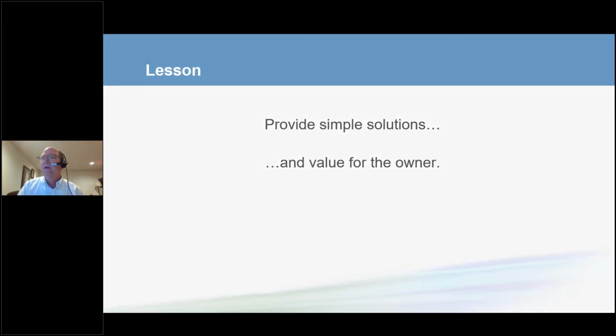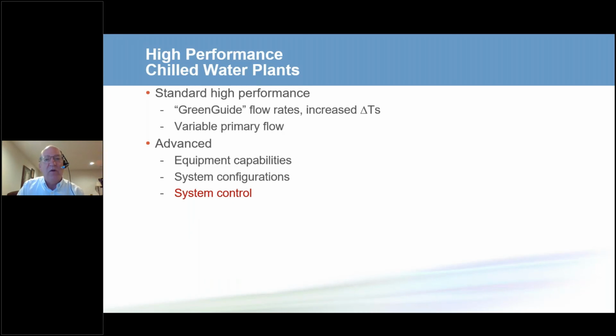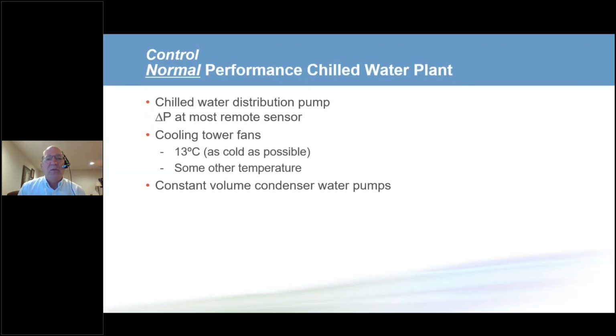The final thing we're going to talk about today before we go to our question and answer is system control. This could be another 60 to 90 minute seminar, but we're just going to take a few minutes to talk about the most used system controls. In a normal performance chilled water system, most chilled water distribution pumps are controlled by having a differential pressure sensor at, quote, the most remote air handler, at a valve somewhere out in the system.